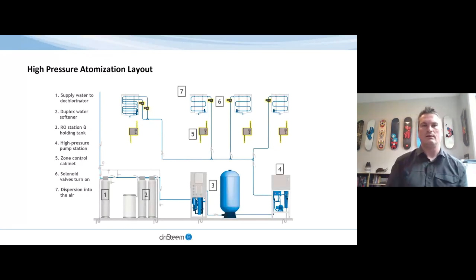So we're looking at dechlorinating the water, removing the chlorine, softening that water and displacing the carbonates, the hard minerals, with soft minerals. This will extend the life of an RO membrane. There's an RO system, which then has a buffer tank. And then we have a high pressure pump. Now the high pressure pump can distribute to 4 different air handlers or 4 different zones, which can then be staged and regulated to modulate based upon the demand coming from those. So we have solenoid valves, which will control the output based upon what that signal is coming in.